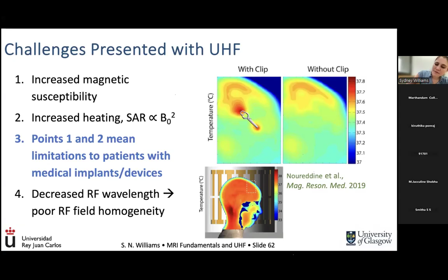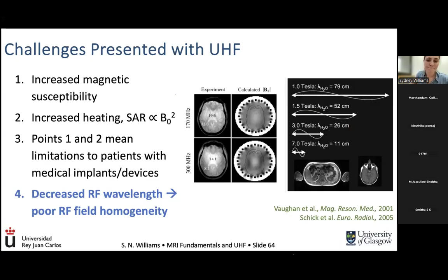On top of that, we do have this decreased RF wavelength with the higher frequency. That actually makes the whole field in which we're generating the spins that are going to precess and create our MRI signal less and less homogeneous. This is a really nice example that I think Shajan will show again: at 3 Tesla, we have a wavelength around 26 centimeters, which means that 26 centimeters will pretty nicely cover the full diameter of the human head. At that level, we can image the brain relatively well without any interference of the wavelength, any central brightening, or any darkening of areas of the brain. But at 7 Tesla, unfortunately, the wavelength is quite low. It's 11 centimeters. And then we start to have these interference effects in the brain.